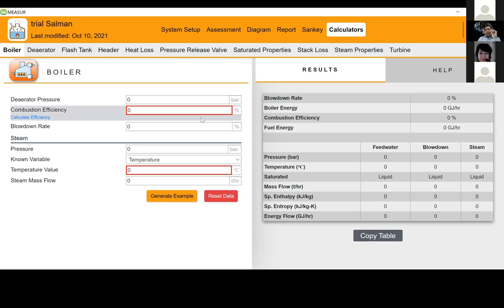Some drawbacks is that it estimates the fuel intake itself. It does not let you enter the actual amount of fuel there. It also does not let you select if you are doing any heat recovery from the stack. There are no options of doing that in the main assessment. So these are the two main drawbacks that I have seen. Third is that because we have selected the solid fuel, it has not provided any option of doing assessment for the filtering process or the water showering process to remove the pollution load or calculating the greenhouse gas emissions, for example. These are the things that are missing. But since we are all experienced auditors, we can use this assessment here and do some of the calculations manually and club them together. So the report can be generated pretty quickly rather than we use a lot of Excel. We can use this and then generate the reports very, very quickly.